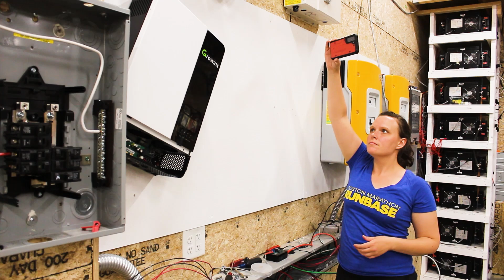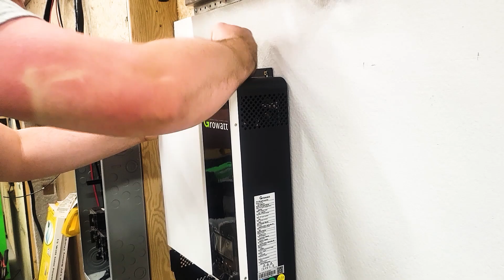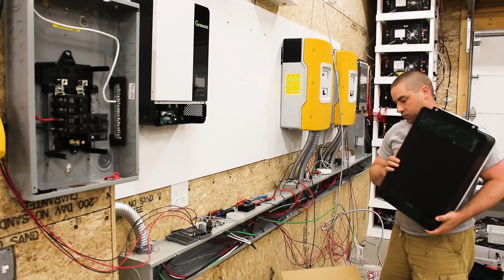Not all inverters do that. It used to be that you'd always buy them as 2 separate components, the charge controller and the inverter. These just happen to have both components built into one box. So I wired the solar PV array, one array into each inverter. Now the built-in charge controllers for these are higher voltage. They go up to 450 volts DC. So when I wired these in, I was able to wire more solar panels in one long string. That means that each array is coming in as only 2 strings. That keeps the wiring pretty small.